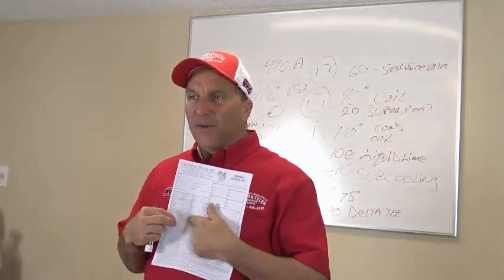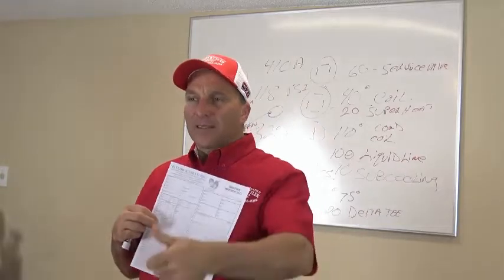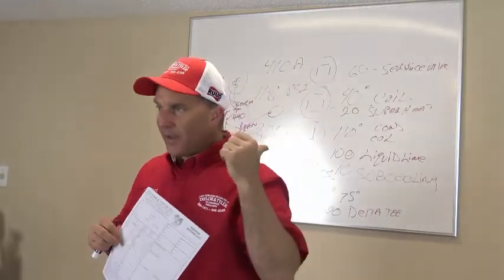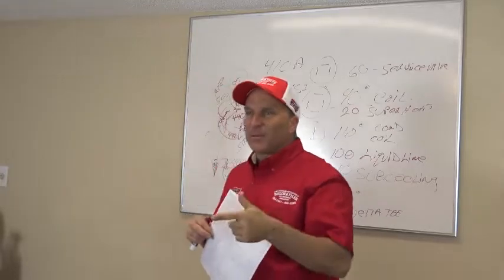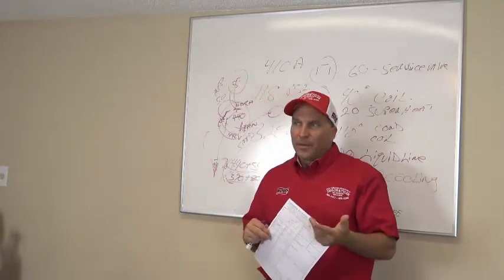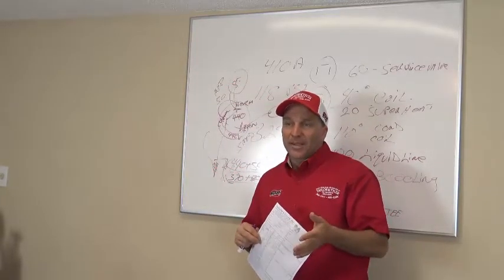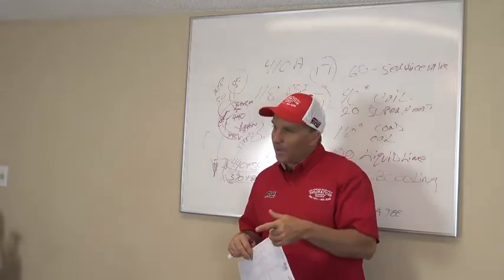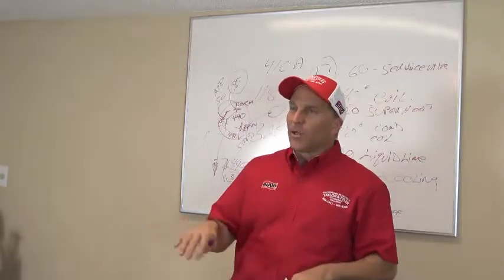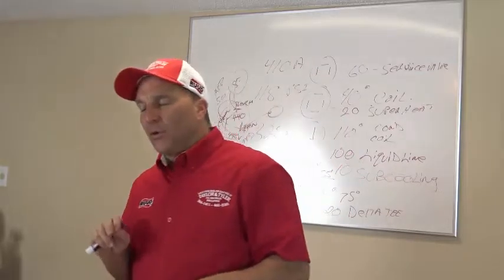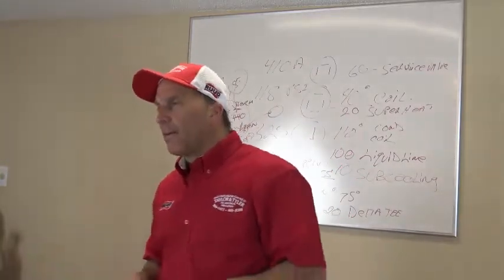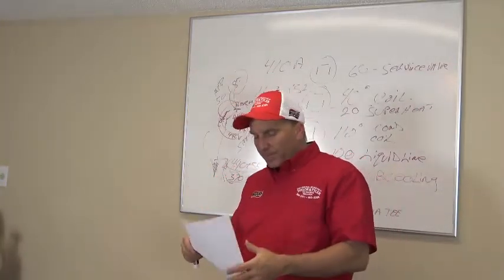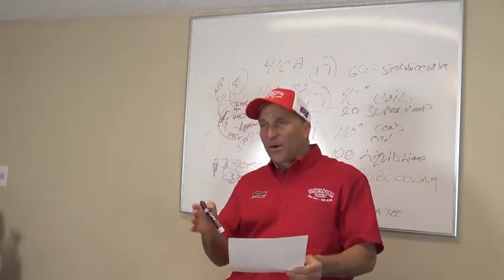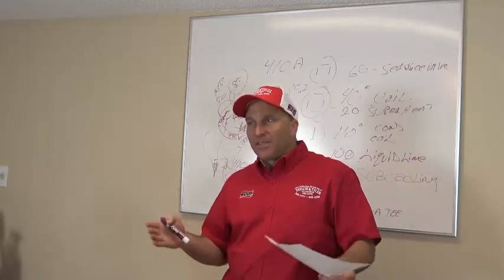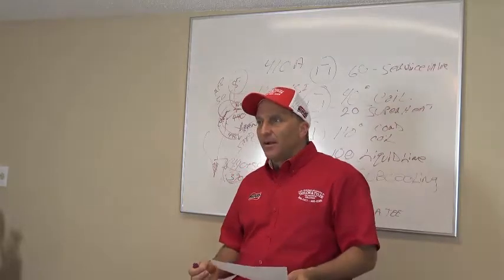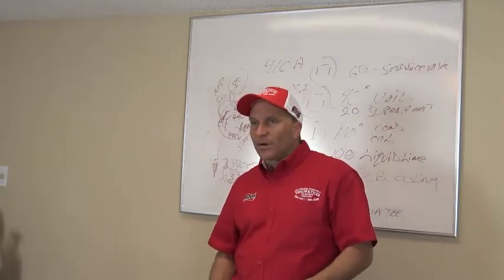And if they're different, like in the disconnect that's sitting out there right now that I showed you, we had a 60 amp and a 40 amp in there, am I correct? Yeah. But the maximum amperage on that system was a 35, I think it was. It was 35. So we literally could pull those two fuses out, put two 35s in there, would be good. Okay. I want people to check that, and I want them to find it. And I want them to see that it's the wrong fuse size in there. And I want them to note it on their paperwork. Okay?